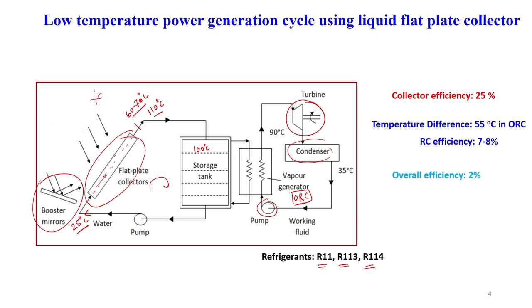Normally, the collector efficiency is about 25 percent. The temperature difference between the entry of the turbine and the condenser is about 55 degrees. If we consider this temperature difference and calculate the Rankine cycle efficiency, it is found to be about 7 to 8 percent. If we combine all those efficiencies, the overall efficiency is found to be about 2 percent. So this is not a very efficient process, but when there is a prime requirement of electricity and solar radiation is available, we can suggest this kind of technology.